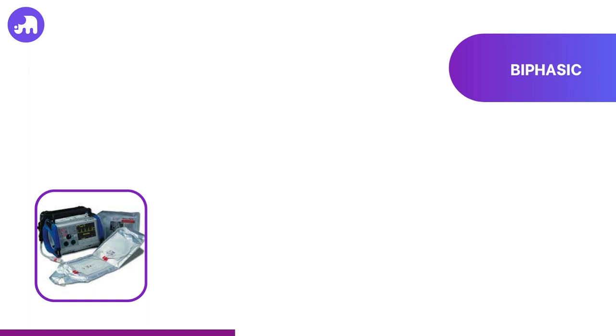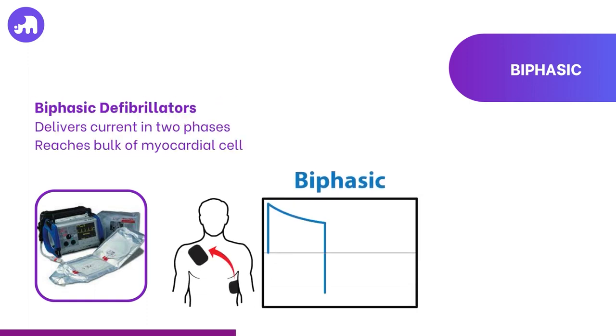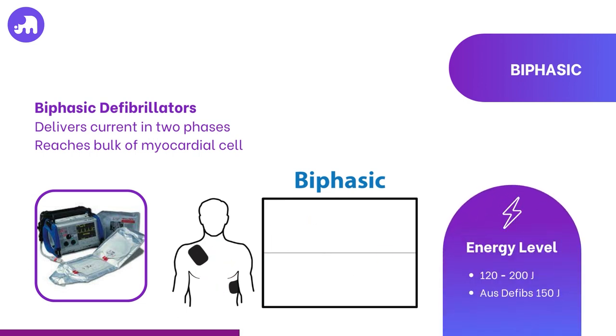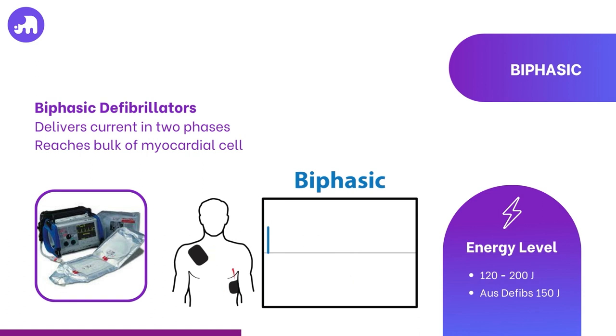In contrast, biphasic defibrillators send the electrical current in one direction and then swiftly reverse its flow, sending it in the opposite direction. This bidirectional flow enhances the chances of successful defibrillation while typically using less energy. For adults, the starting energy levels with biphasic defibrillators generally range from 120 to 200 joules. If the initial shock doesn't achieve its intended result, the energy level can be adjusted based on the patient's response and the device's recommendations.